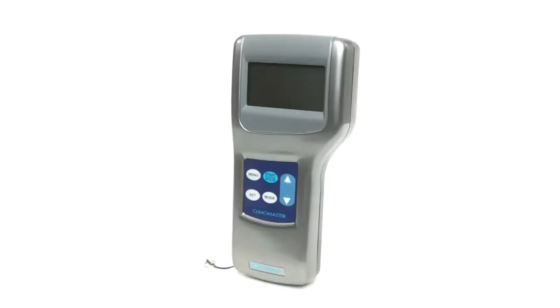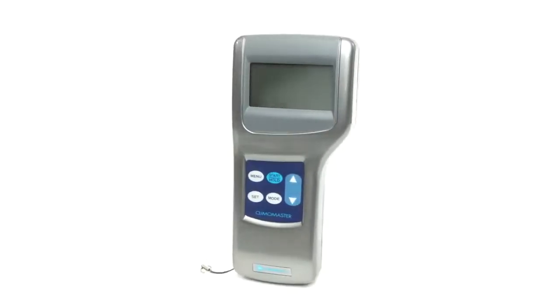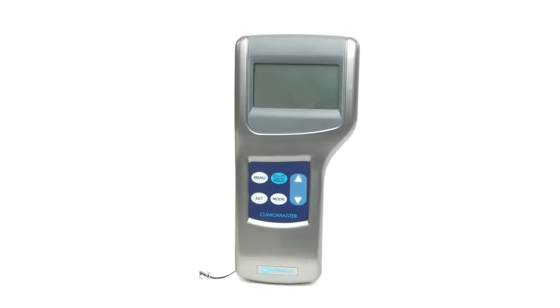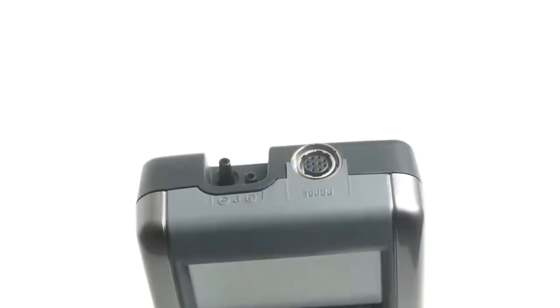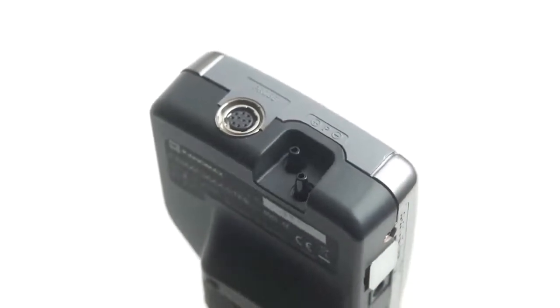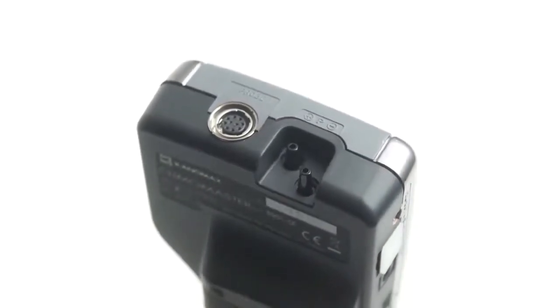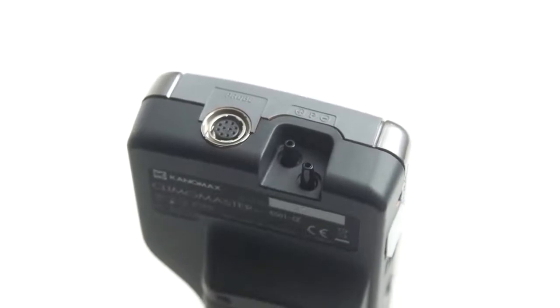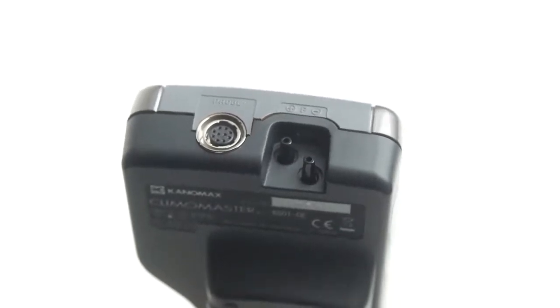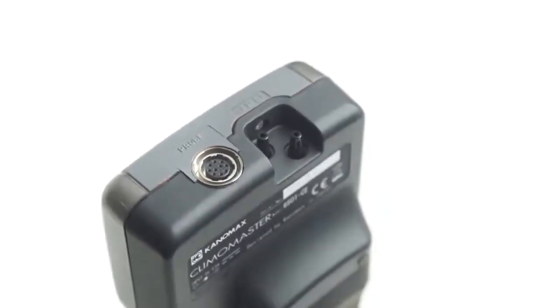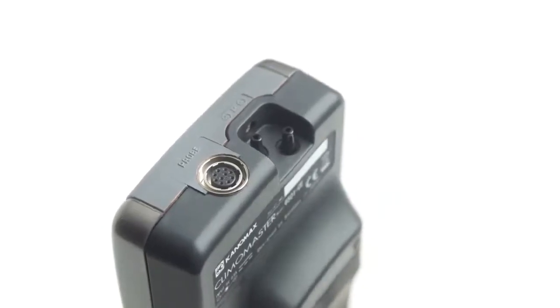To operate the Kanomax Climomaster, let's first go over the external controls, inputs, and outputs of your device. On top of the main body, you'll find 3 ports. The 2 ports grouped together are your negative and positive pressure ports. These should remain open and clear of any blockages whenever you decide to zero your device before measuring pressure. And the larger port is the probe socket, where you connect your cables and probes.